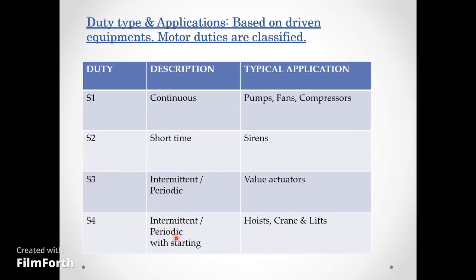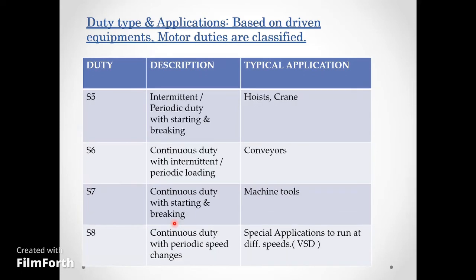S4 is intermittent periodic duty with starting, used for hoists, cranes, and lifts where the motor starts intermittently. S6 is continuous duty with intermittent periodic loading, used for conveyors. S7 is continuous duty with starting, used for machine tools. S8 involves variable speed drives for special applications.